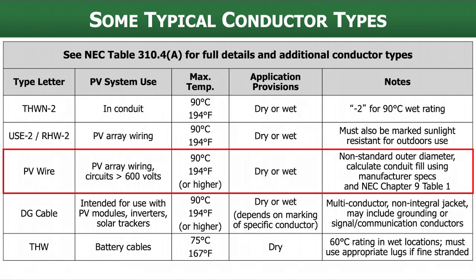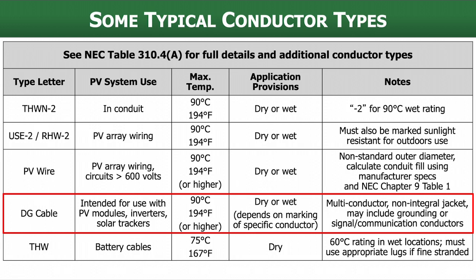Another PV-system-specific conductor type is DG cable — distributed generation. This is for use with modules, inverters, and trackers. A common application is as part of a listed cable assembly that goes along with some types of micro inverters. It can have different numbers of conductors — it's a multi-conductor jacketed cable that could include grounding wires and signal and communication wiring. There's a lot of flexibility for what goes inside. Just like PV wire, it's not in Table 310.4A because it is somewhat new and doesn't yet have a wide range of applications outside the solar industry.